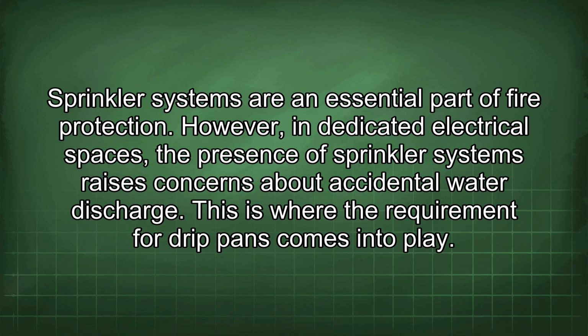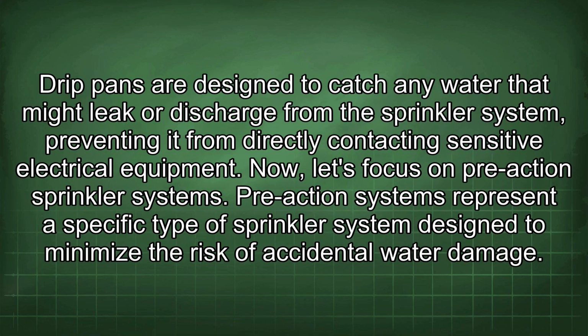However, in dedicated electrical spaces, the presence of sprinkler systems raises concerns about accidental water discharge. This is where the requirement for drip pans comes into play. Drip pans are designed to catch any water that might leak or discharge from the sprinkler system, preventing it from directly contacting sensitive electrical equipment. Now let's focus on pre-action sprinkler systems.